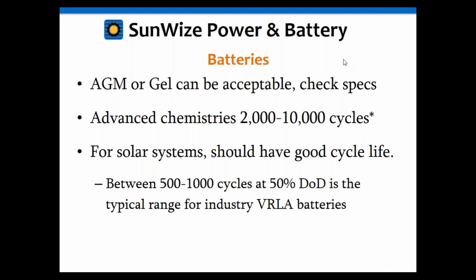You should be getting somewhere around 500 to 1,000 cycles out of your valve-regulated batteries at 50% depth of discharge. The better ones will be more in the 1,000 cycle range, and that's what gets you around 5 to 8 years, based on a 5-day autonomy battery, so they're only cycling about 20% per day on average.